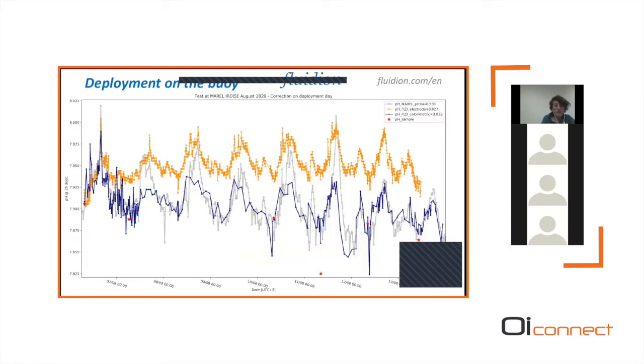Then these are the data that we obtained from this deployment. You can see in blue the data obtained from the colorimetric analyzer. In yellow, the data obtained from the electrode. In gray, the data obtained from the multi-parameter probe, which is originally installed on this buoy. And in red, these stars are the data from the samples. What you can see is that the colorimetric analyzer and the multi-parameter probe both follow this decreasing trend that is observed with the samples.